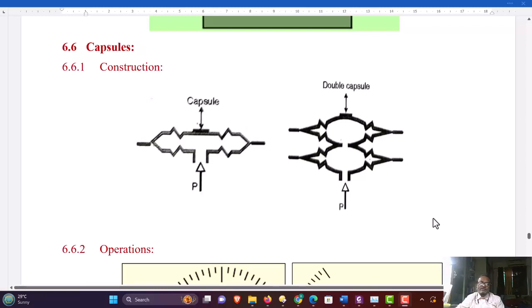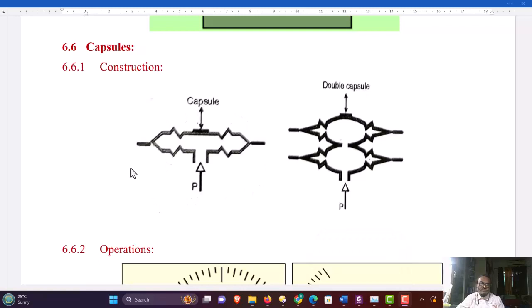The other type of primary sensor is a mechanical capsule. The construction of the mechanical capsule is shown here. The capsule is formed by welding two flexible diaphragm type discs with corrugation, shown here with a pressure port, so that from this port the pressure fluid can go inside, and when pressure is applied the capsule will expand and the movable end of the capsule will be deflected. Here a double capsule is shown in the figure.